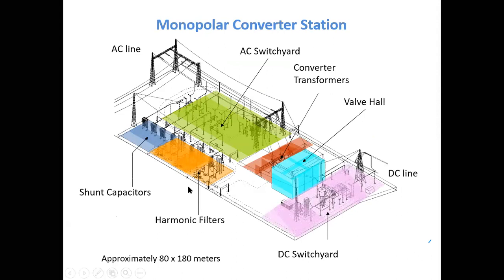So any terminal station, suppose it is, we can say, a rectifier station, so input is from here. From the AC switchyard, you will energize the valves, but in the shunt connection, there will be the filters to filter out the harmonics, and there are the shunt capacitors. Why are shunt capacitors provided? To provide the additional reactive power. Suppose not that much generation is available on our bus, so we have to provide the additional reactive power. For that, shunt capacitors are used, harmonic filters are used. There might be band pass filter, high pass filter, like that. And this is the AC switchyard. Here circuit breaker, isolators, lightning arrestor, all the equipments are there.